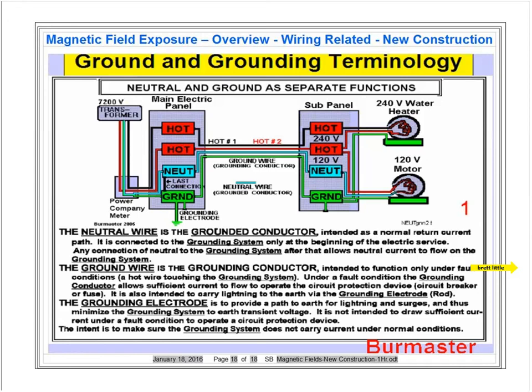And the reason why this happens is because electric current will take all available paths to get back to the source. It takes the path of least resistance primarily, but not exclusively. And then if you take that concept within a house and extrapolate it to the whole neighborhood, you can have 8 amps coming into the building on the hot wires between the two legs, and you should have 8 amps going back, but you could have 7 going back because 1 amp is going on the grounding conductor to the metal water pipe and out the front yard on the metal water service supply pipe, and also the sheathing of the TV cable, by the way, is another but parallel path.